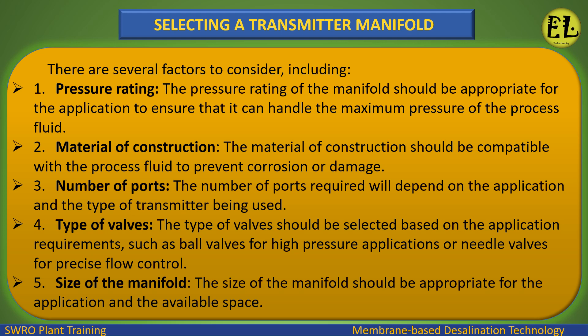Selecting a transmitter manifold — there are several factors to consider: 1. Pressure rating: the pressure rating of the manifold should be appropriate for the application to handle the maximum pressure of the process fluid. 2. Material of construction: should be compatible with the process fluid to prevent corrosion or damage. 3. Number of ports: depends on the application and type of transmitter being used. 4. Type of valves: selected based on application requirements, such as ball valves for high-pressure applications or needle valves for precise flow control. 5. Size of the manifold: should be appropriate for the application and the available space.